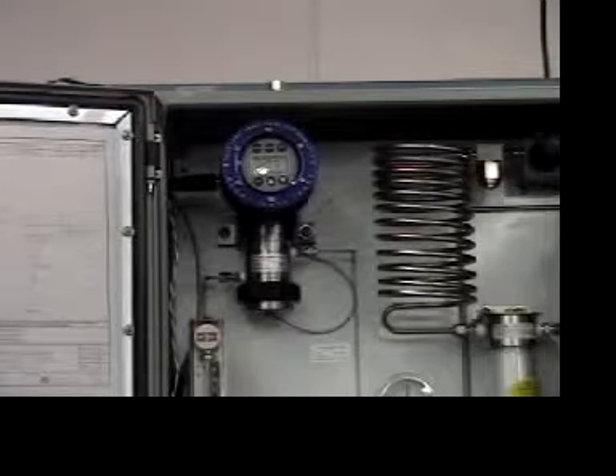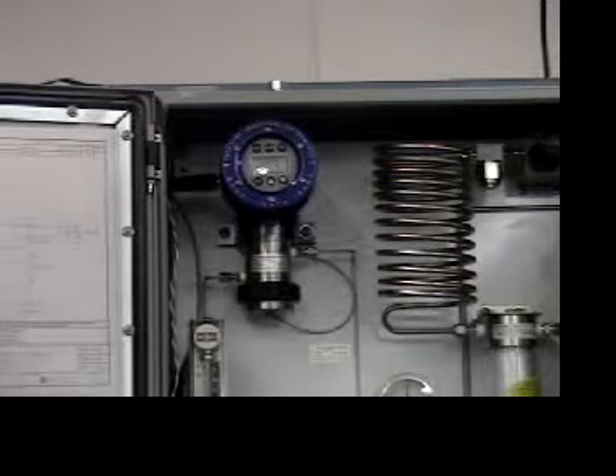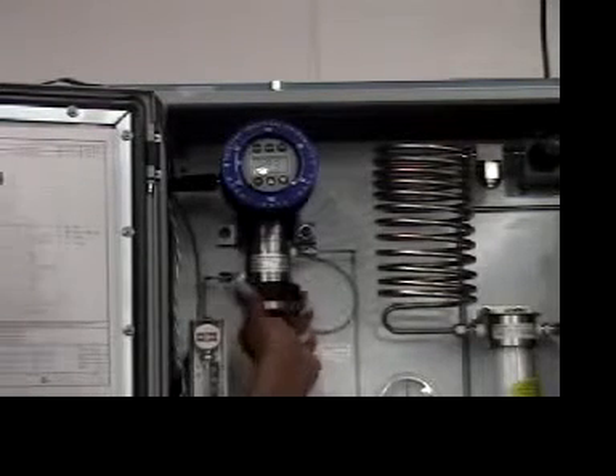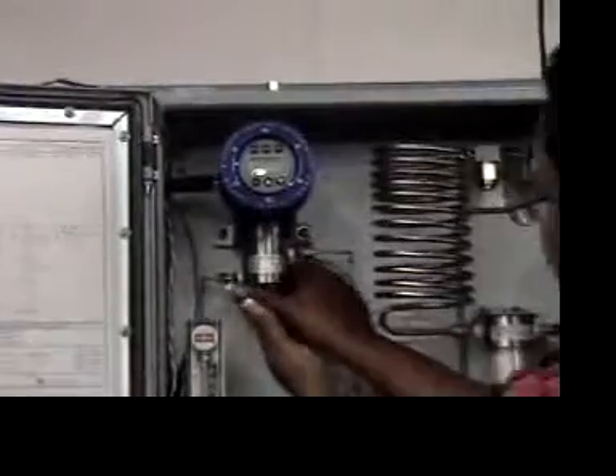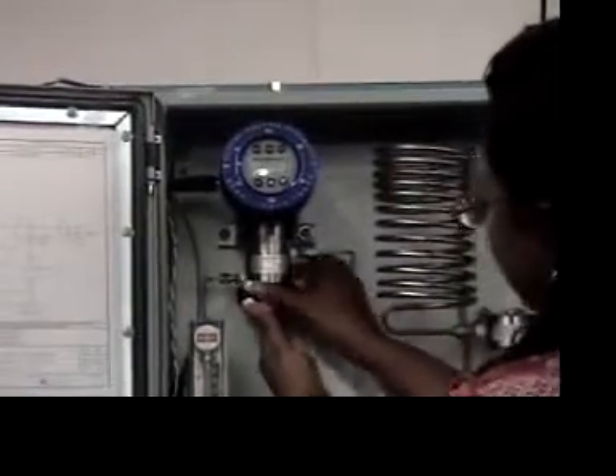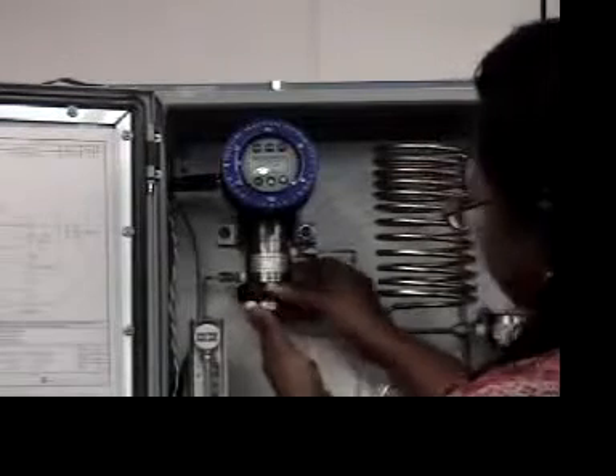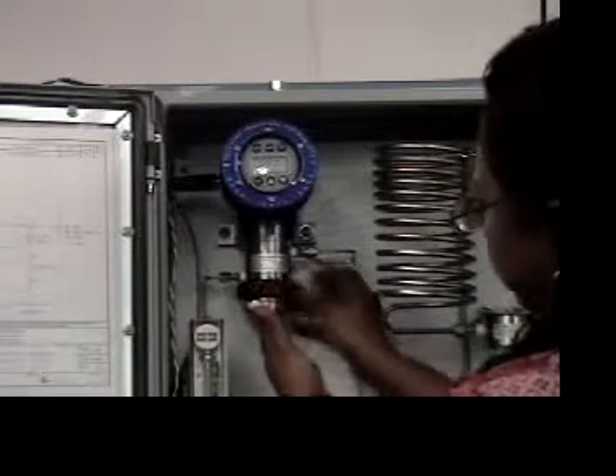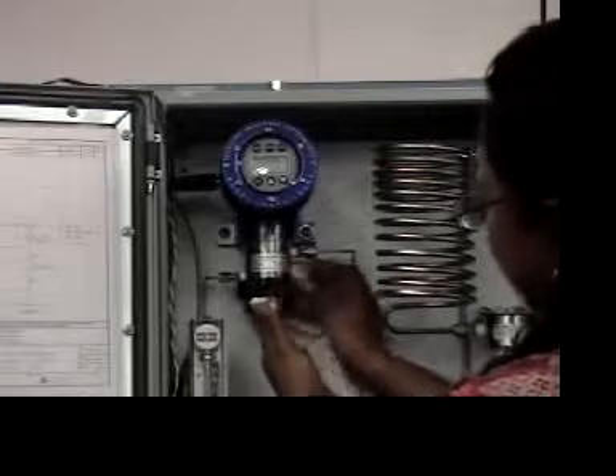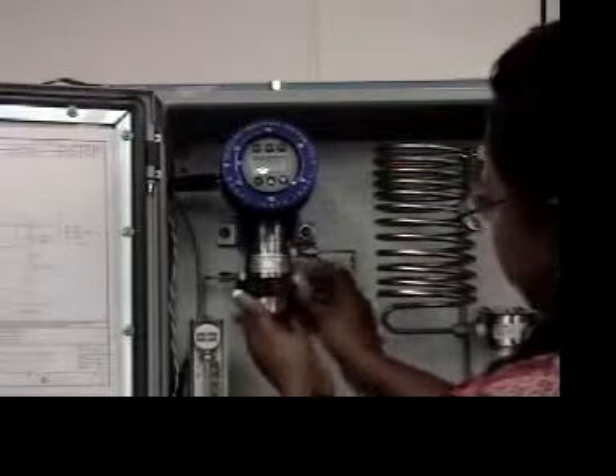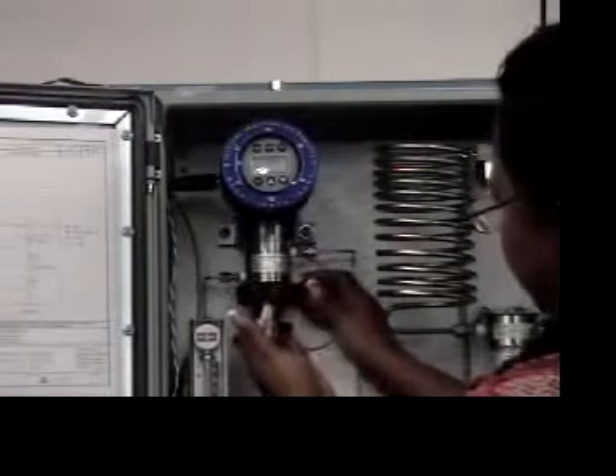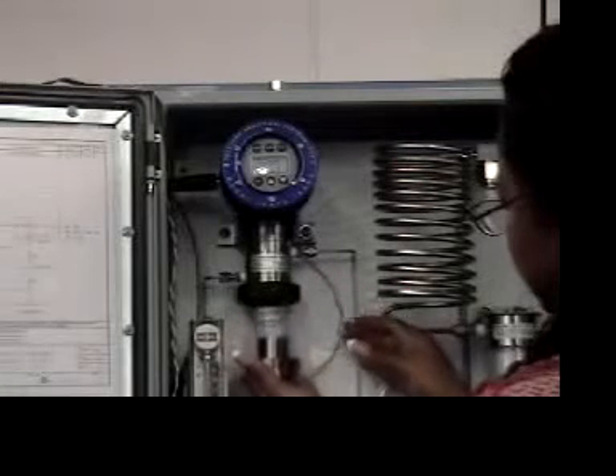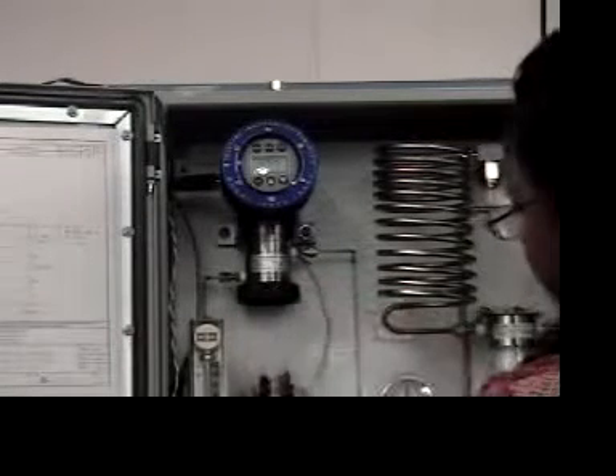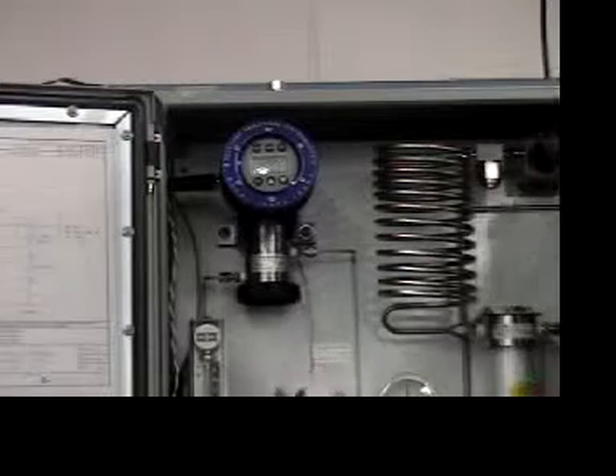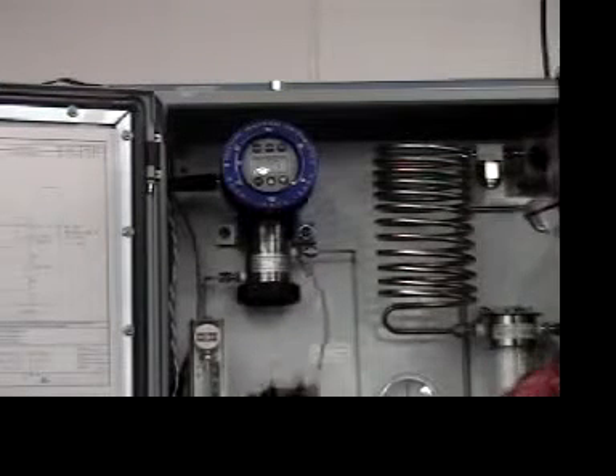I will demonstrate the installation of the oxygen sensor into the transmitter. To open the sensor holder, you want to turn this lever counterclockwise just to loosen the plug that will come out in your hand. Your fingers should be on the bottom to pull the cap off. It's attached, so it's not going anywhere.